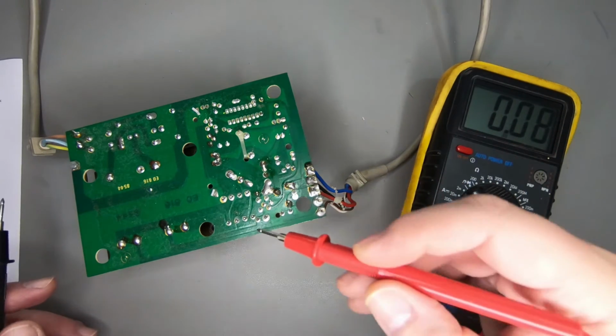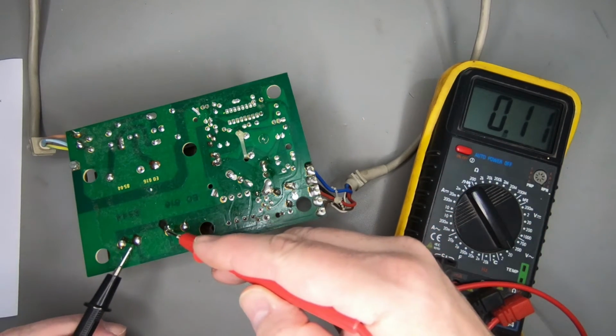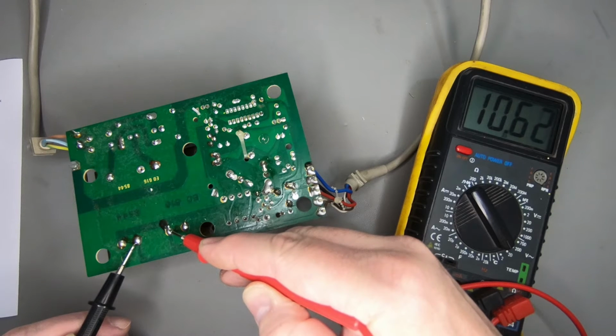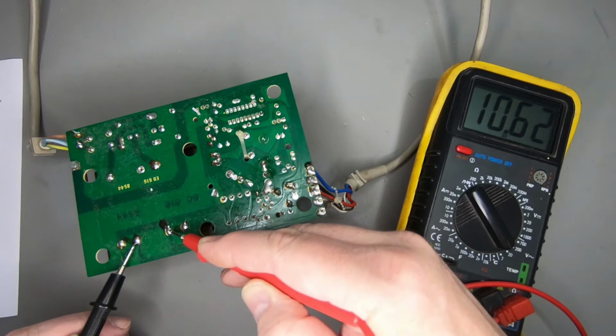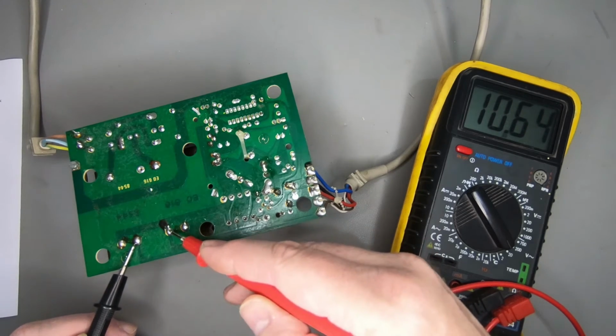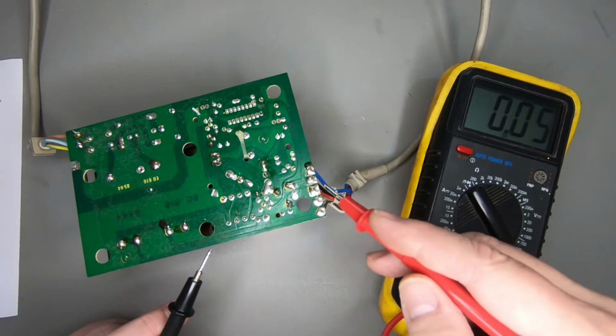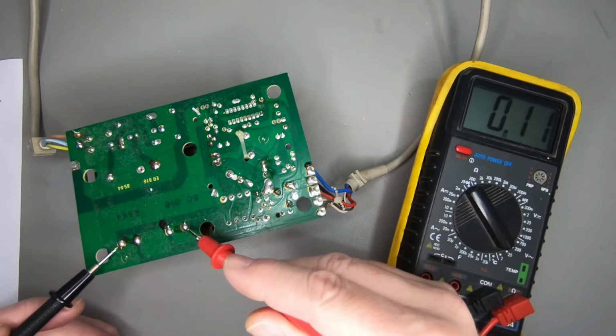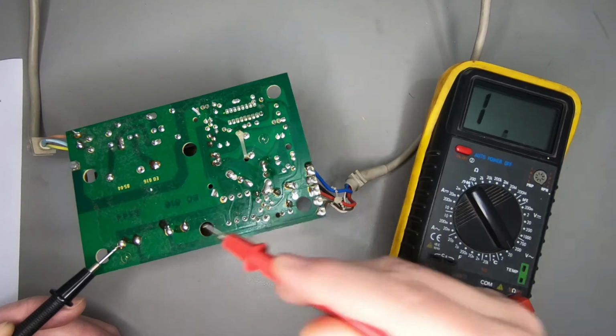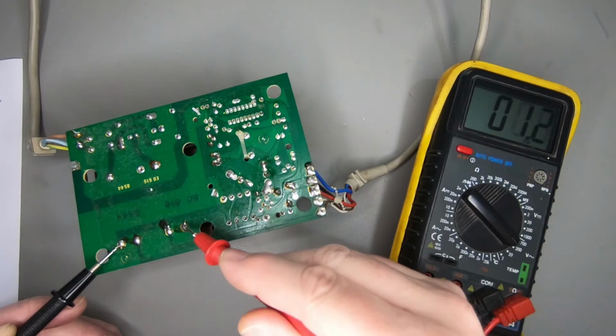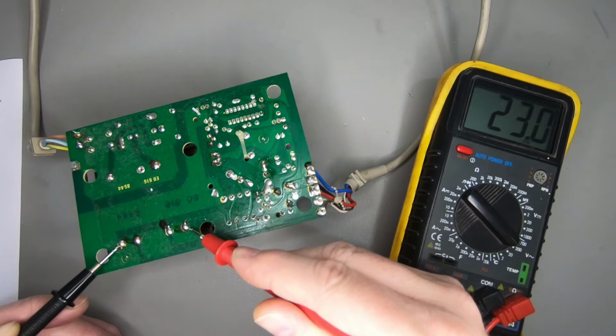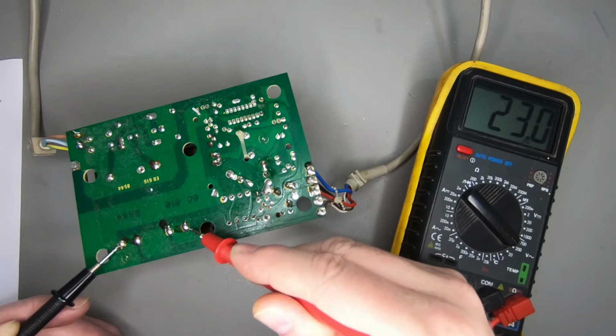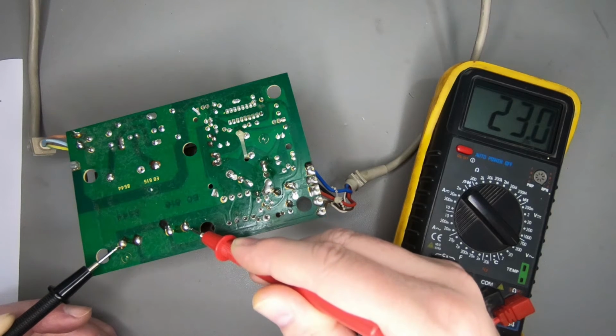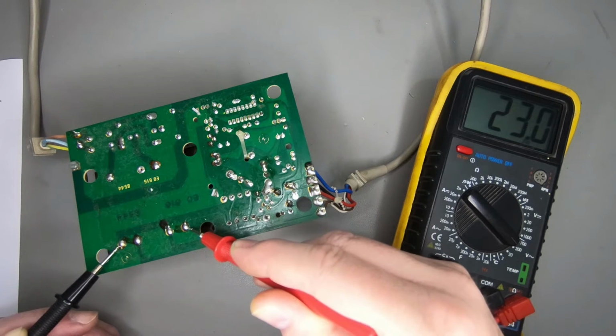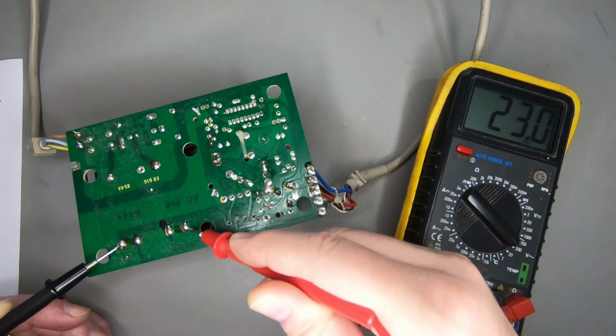So let's test the 9 volts tap on the transformer first. Yeah, 10.6. That's AC, of course. And this looks like it just goes through that fuse and then straight out to the cables. The other two taps on the outside, that's for the 5 volts. That's reading 23 volts AC. It's quite high, I would have thought, to regulate down to 5, but it must be right.